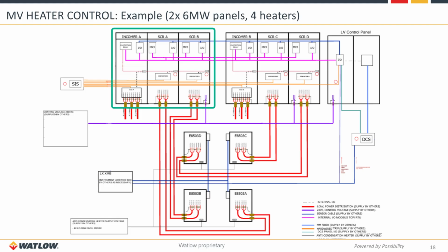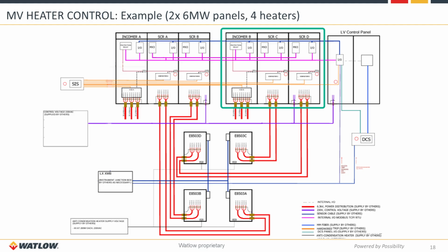So you have group 1 up here that has an incomer and 2 SCRs, and group 2 here that also has an incomer and 2 SCRs. These are feeding 4 heaters, which are depicted down here. These are the heater enclosures that are within the system. This particular system has redundancy built in, which is why they chose to go with 2 separate groups of cabinets and 2 separate groups of heaters.